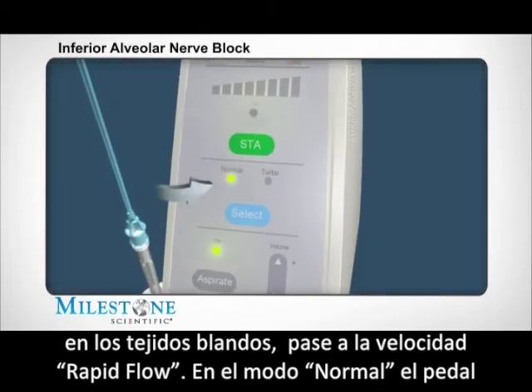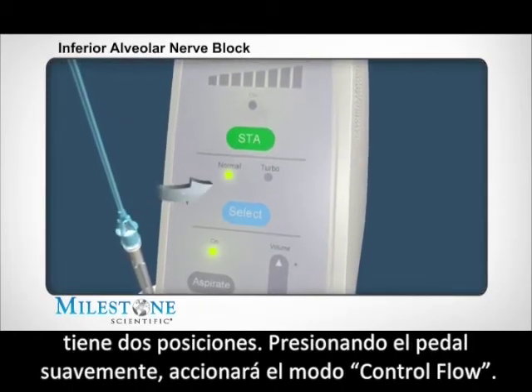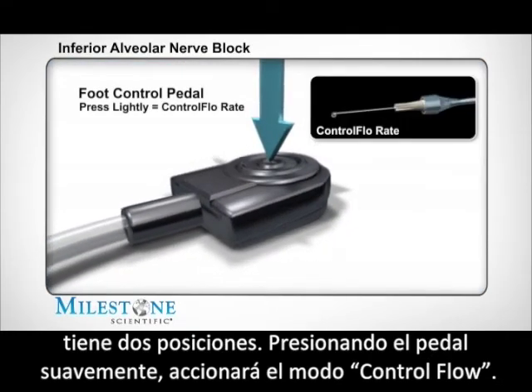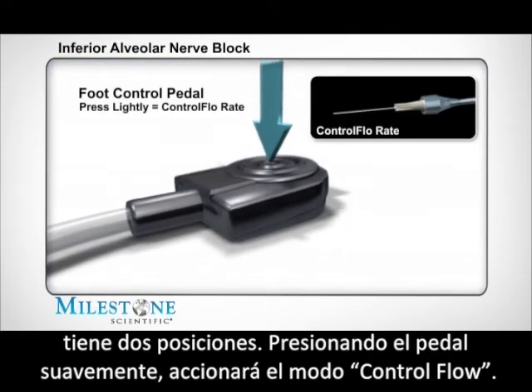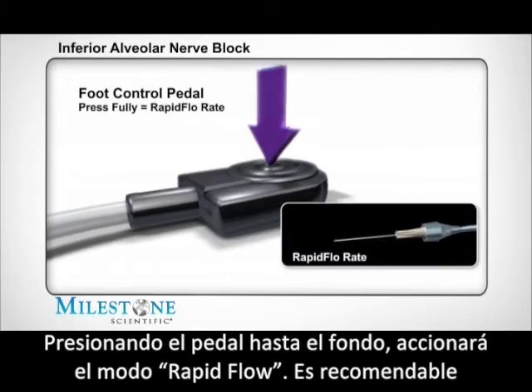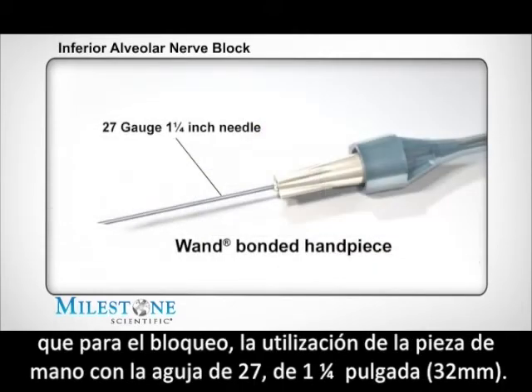In the normal mode, the foot control has two distinct positions. Depressing the foot control lightly allows you to enter the control flow rate. Fully depressing the foot control allows you to enter into the rapid flow rate. It's recommended that you use a 27 gauge, one and a quarter inch needle to perform the inferior alveolar nerve block.